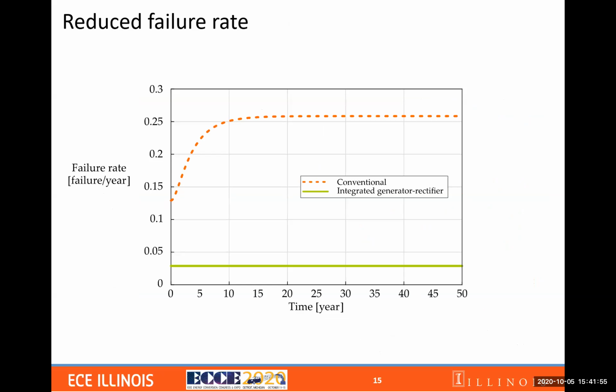On top of that, because we have been relying a lot on diodes, and we reduce the voltage requirements on the active rectifier, we see a big decrease in the failure rate of the whole system. We look at a time frame of 50 years, which far exceeds the lifetime of a wind turbine system, and we see the failure rate could be reduced by almost 10 times. With the failure rate reduced, you can operate the system for more hours per year, and that translates to extracting more power from your wind turbine as well.